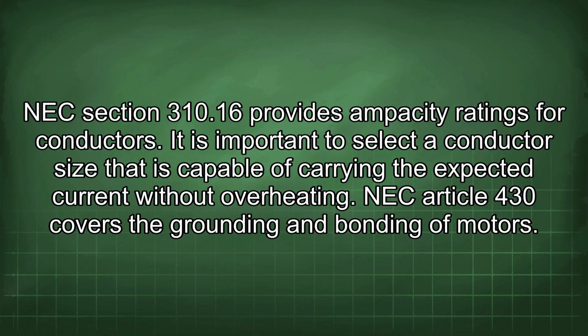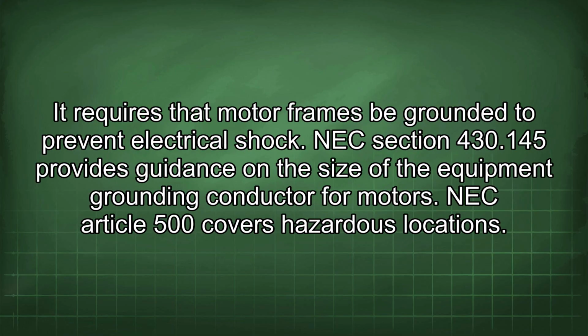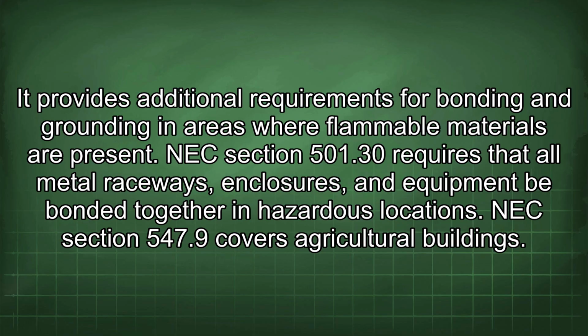NEC Article 430 covers the grounding and bonding of motors. It requires that motor frames be grounded to prevent electrical shock. NEC Section 430.145 provides guidance on the size of the equipment grounding conductor for motors. NEC Article 500 covers hazardous locations. It provides additional requirements for bonding and grounding in areas where flammable materials are present. NEC Section 501.30 requires that all metal raceways, enclosures, and equipment be bonded together in hazardous locations.